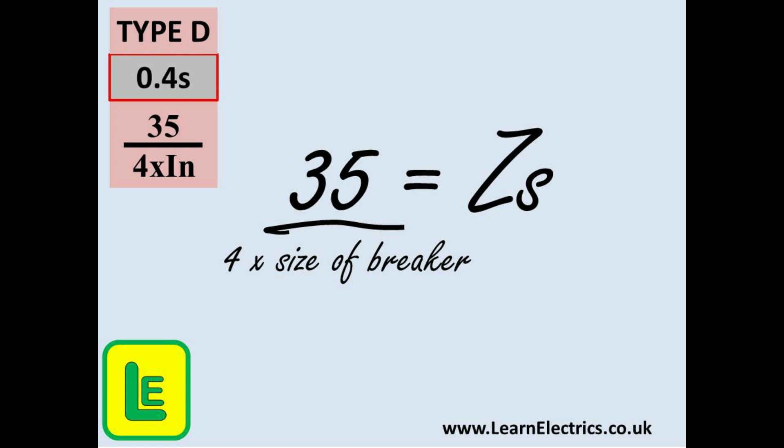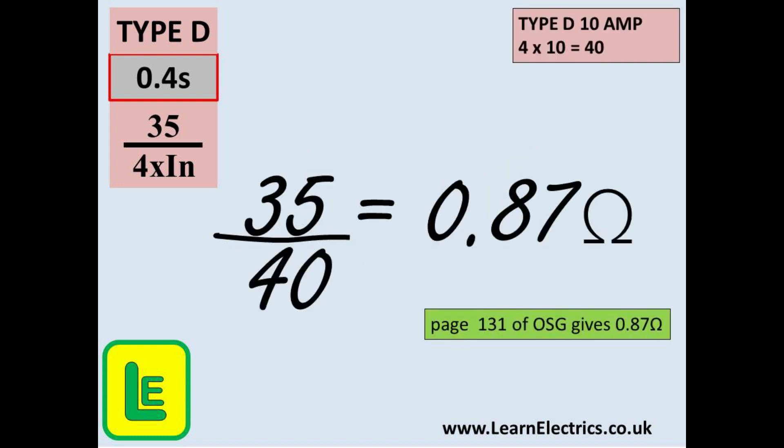Okay back to 0.4 seconds disconnection times and type D breakers. Now we must divide the number 35 by 4 times the breaker rating because the type D is even less sensitive. Showed at the top left is the calculation using symbols: 35 divided by 4 times IN. If we stay with the 10 amp circuit breaker, 4 times 10 is 40. Our calculation then is 35 divided by 40 and this will give us 0.87 ohms. Compare this to the book which is 0.87 and again we are spot on.